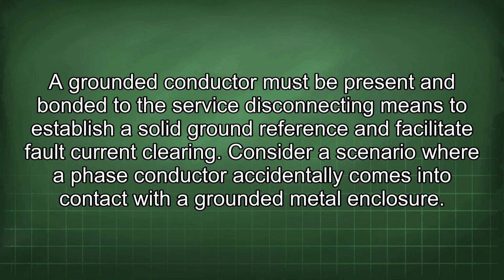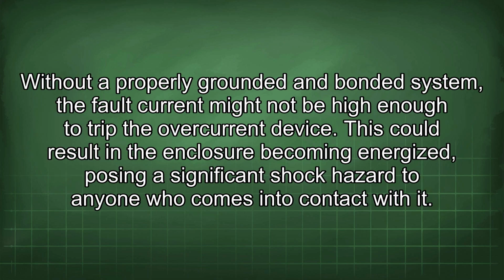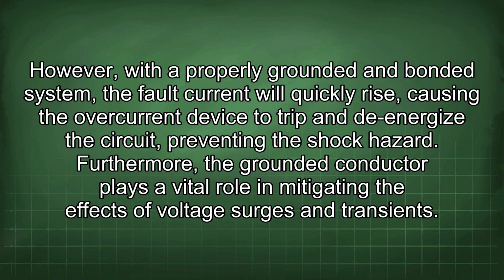Consider a scenario where a phase conductor accidentally comes into contact with a grounded metal enclosure. Without a properly grounded and bonded system, the fault current might not be high enough to trip the overcurrent device. This could result in the enclosure becoming energized, posing a significant shock hazard to anyone who comes into contact with it. However, with a properly grounded and bonded system, the fault current will quickly rise, causing the overcurrent device to trip and de-energize the circuit, preventing the shock hazard.